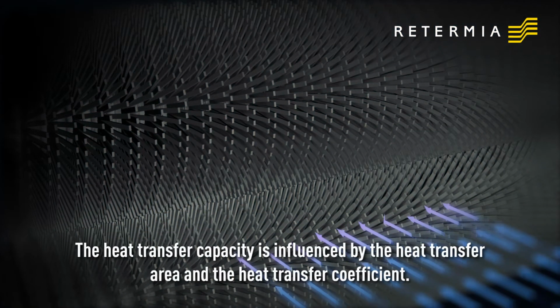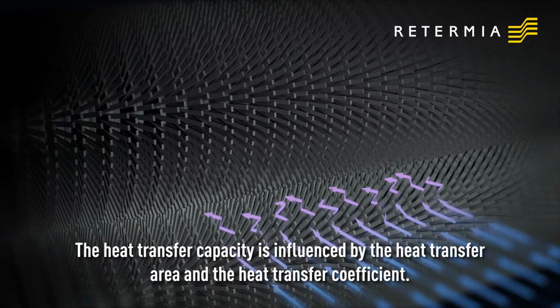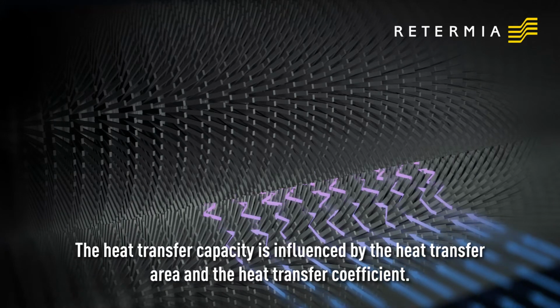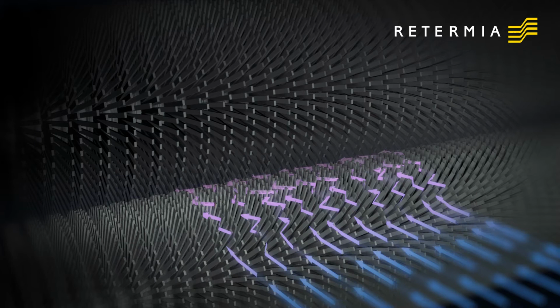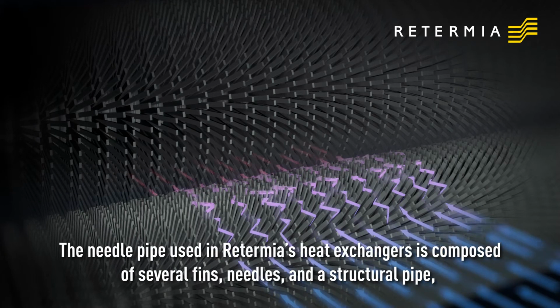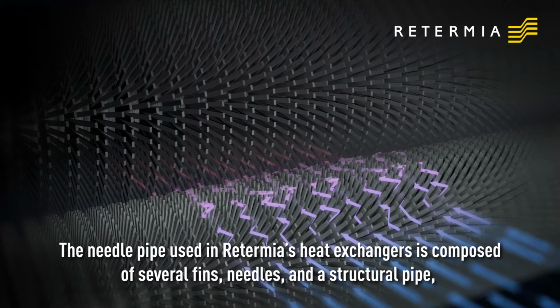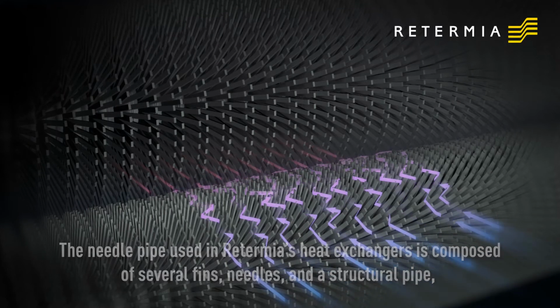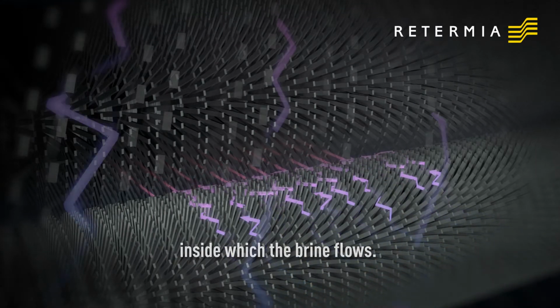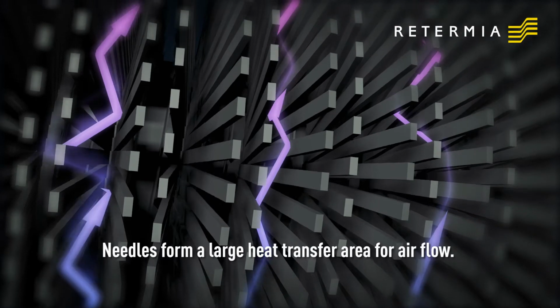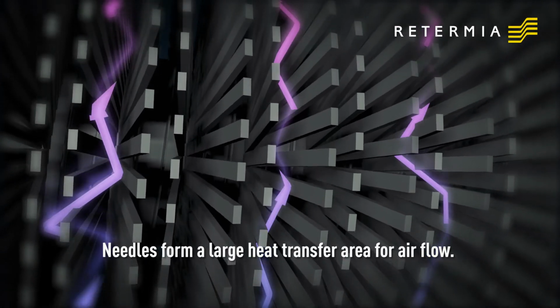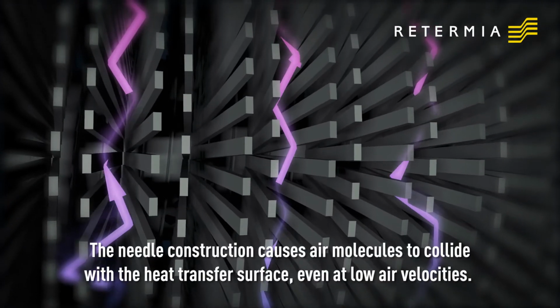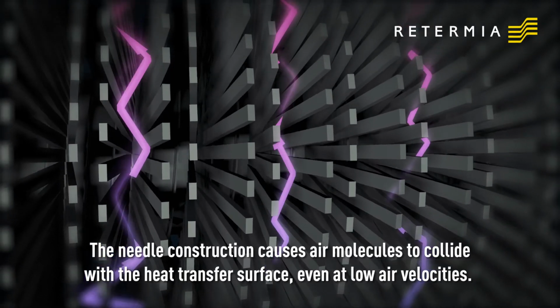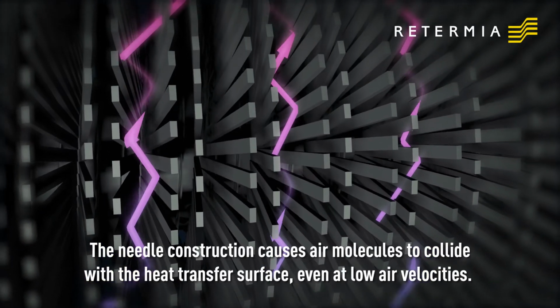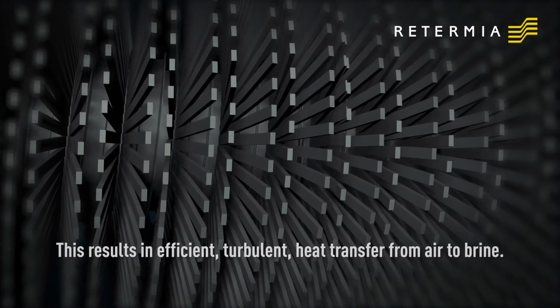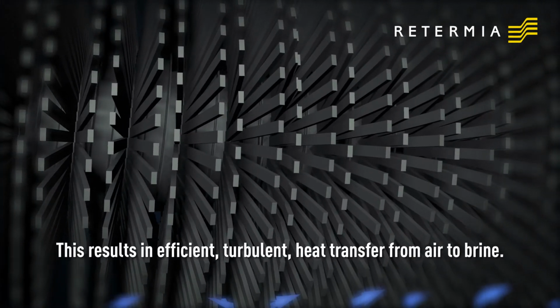The heat transfer capacity is influenced by the heat transfer area and the heat transfer coefficient. The needle pipe used in Retermia's heat exchangers is composed of several fins, needles, and a structural pipe, inside which the brine flows. Needles form a larger heat transfer area for airflow. The needle construction causes air molecules to collide with the heat transfer surface even at low air velocities. This results in efficient, turbulent heat transfer from air to brine.